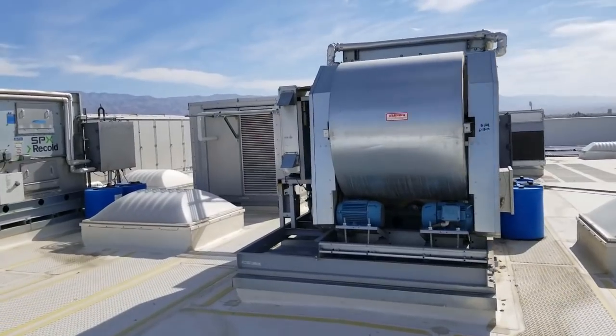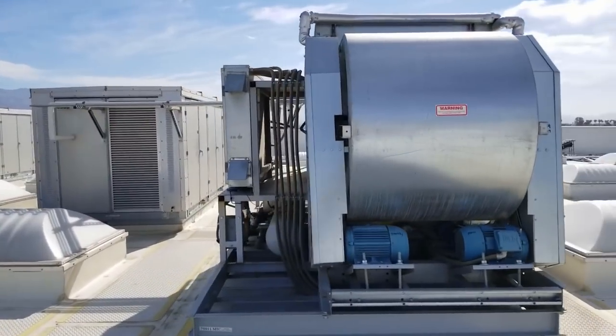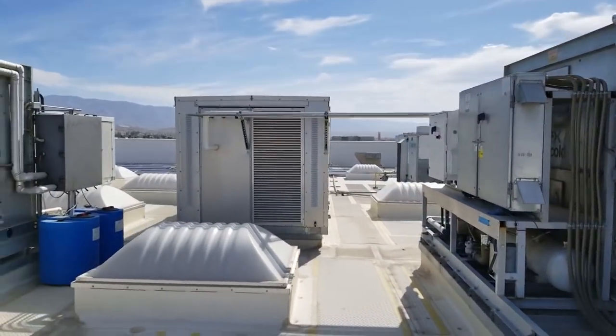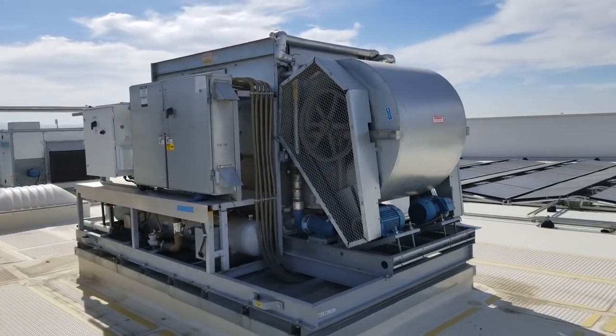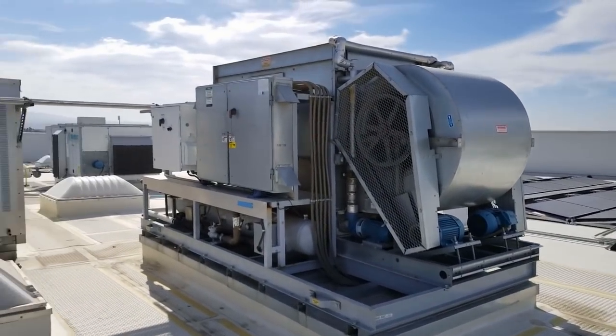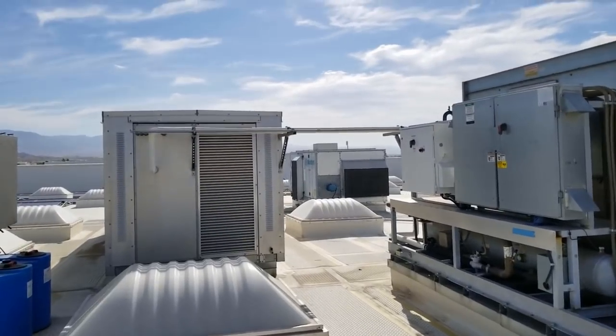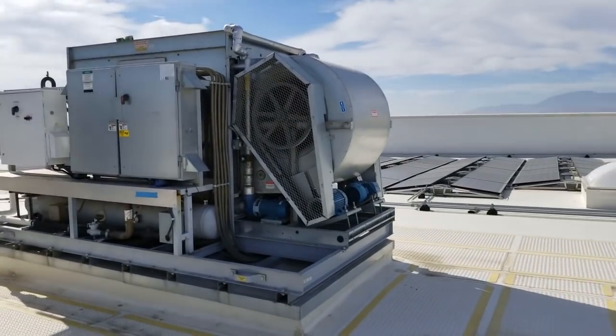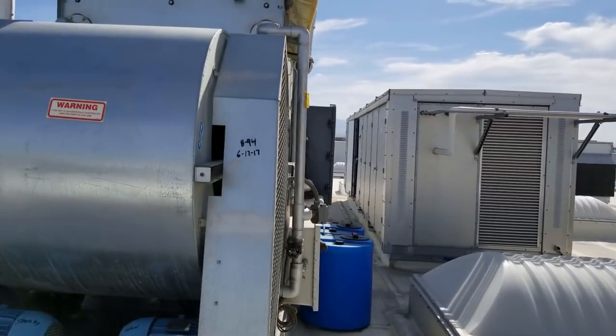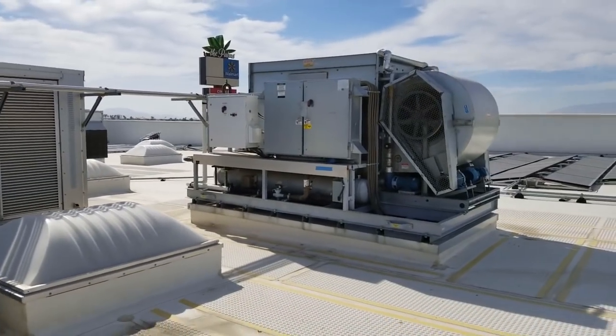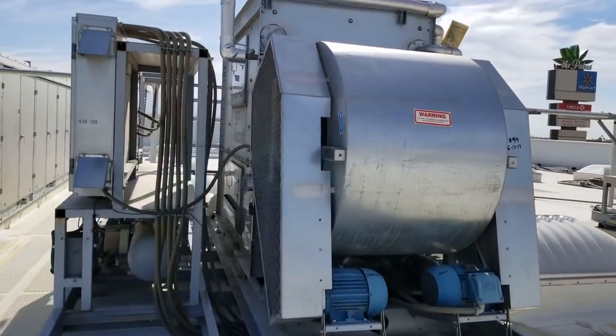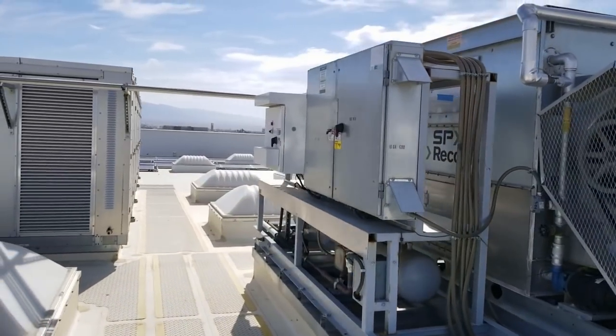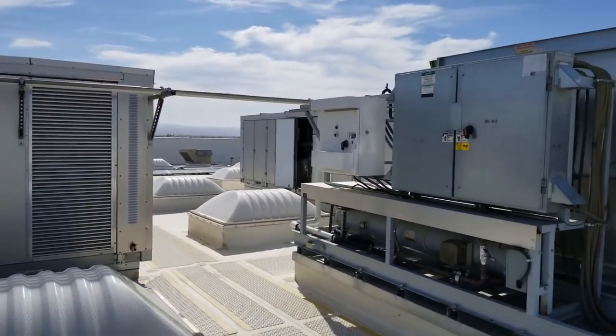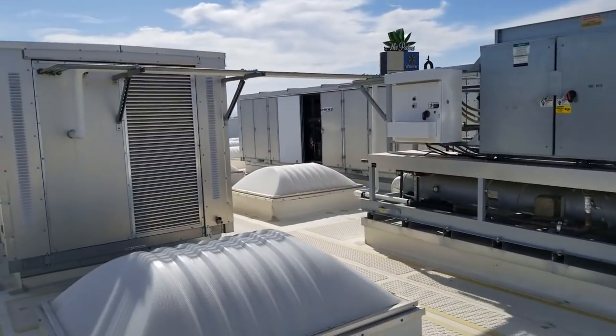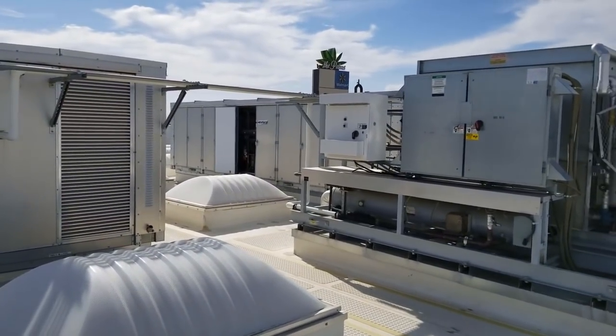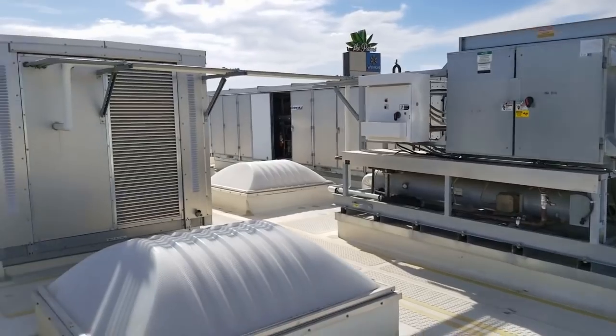They have glycol, rack B and C. And I like this setup here. They have an evaporative condenser attached to each one. So a dedicated evaporative condenser to a rack. That's rack C for Charlie. I got rack B right there. Someone left the door open. Both of them are glycol.